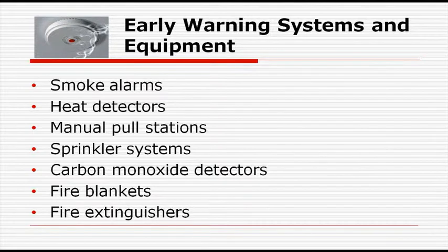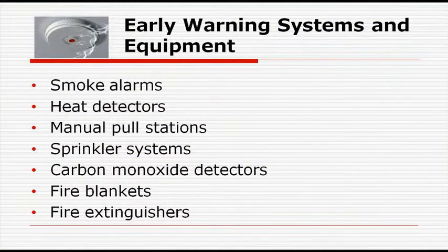Care and maintenance for smoke alarms. Basically, if an alarm occurs, within 10 days that alarm needs to be checked. And if it's not working properly, it needs to be replaced within 5 days. So, the location of smoke detectors. A smoke detector is located at the top of every open stairway, on the hallway side of every enclosed stairway on each floor level, spaced not more than 30 feet apart in corridors, in each common room, living room, dining room, family room, each resident bedroom, in all non-resident living areas, except the furnace, bathroom, kitchen, and laundry room.